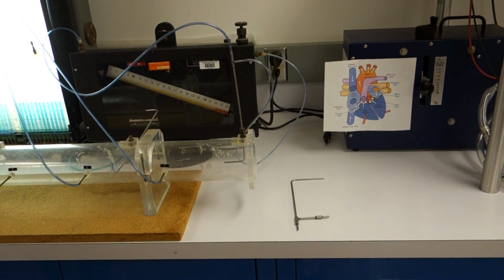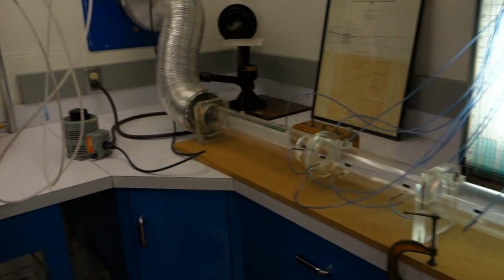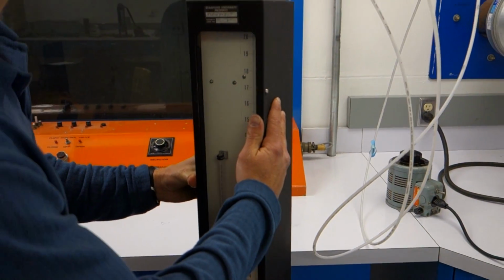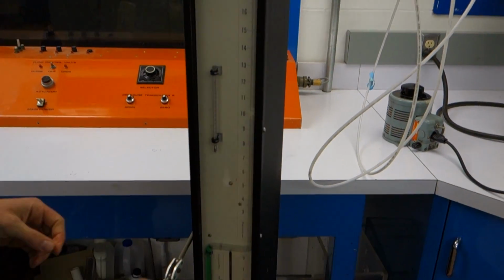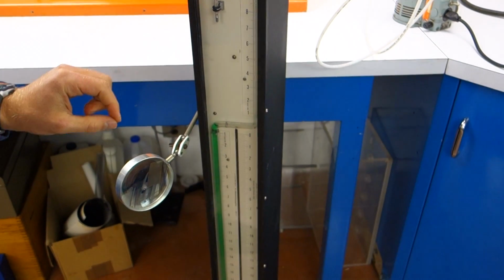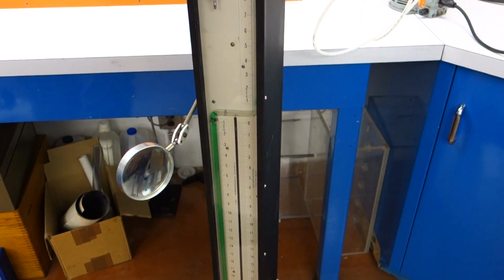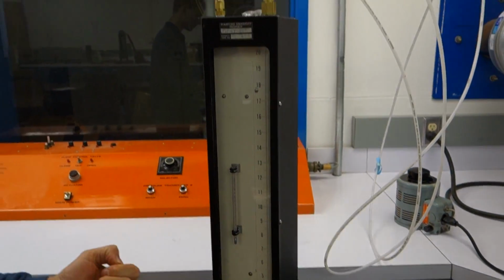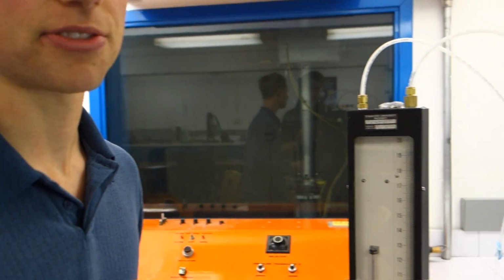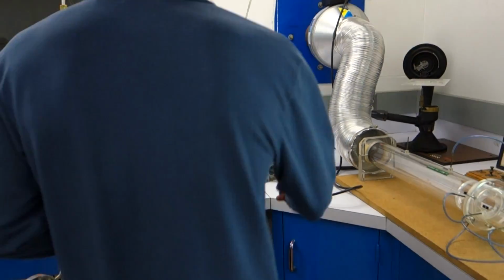What we're going to use though is this floor manometer to measure the delta P. So I did not zero this thing before I turned it on. What I'll do is turn the blower off for a second, zero it, and then turn the blower back on.